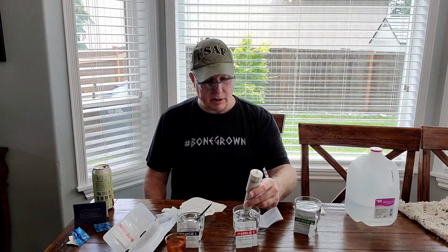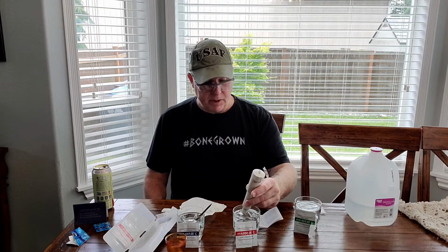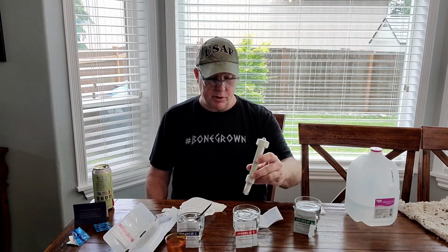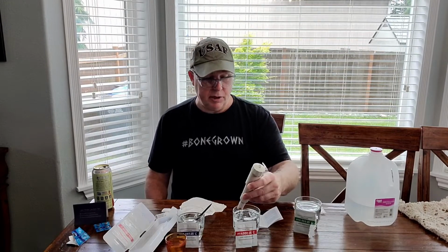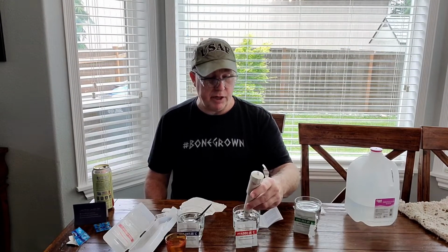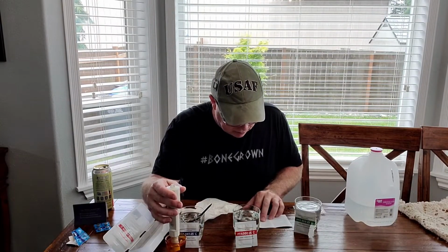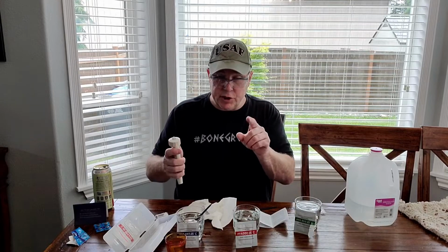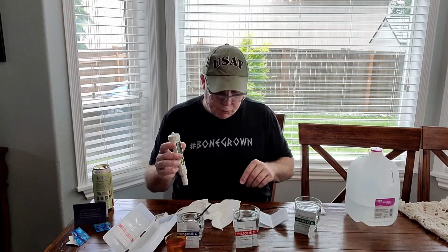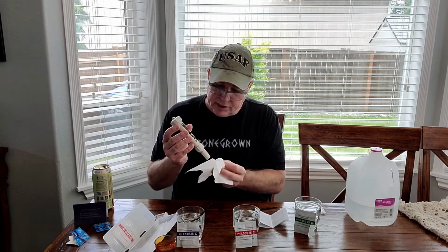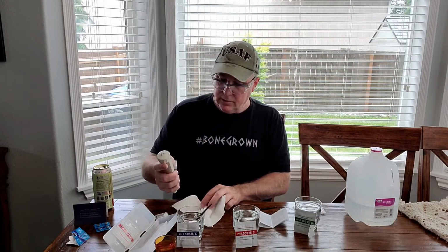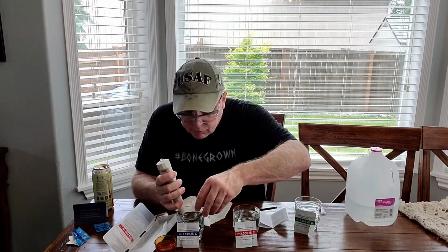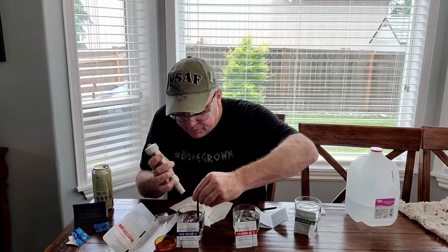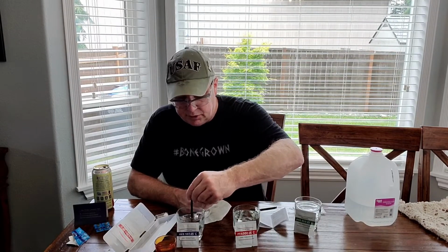So I hit the button for 1 second, and I'm going to go ahead now and turn it off. I'm going to just turn it back on to see what the reading is. It's at 3.99. Clean the electrode with the distilled water, and I'm going to do the third calibration on the 9.18. I'm just doing a little dab here and I'm drying it off. So I'm going to put it in the solution. I want to make sure, see I had a little bit on the bottom, so I want to make sure it's stirred completely.